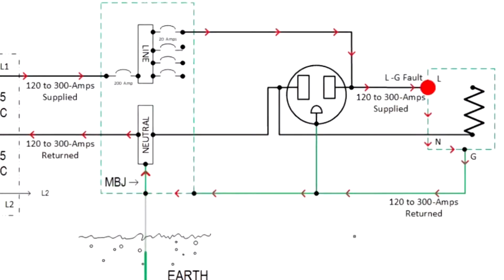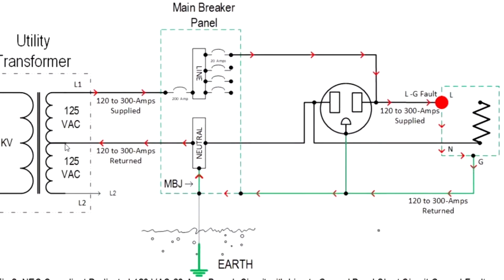Okay, now let's take a look at a fault condition. For whatever reason, the line conductor inside the chassis has fallen off and is touching the chassis, or the line cord got pinched, whatever may have happened. So now we have 120 volts in contact with the chassis, and now the ground completes the circuit. If we follow the current, we can see the current path is off the equipment ground. It goes straight back to our neutral bus inside our main breaker panel and returns to the utility. Now, since there is no more load device from line to neutral, it's line to ground, it's a short circuit. And being a short circuit, it's going to draw, should be, 120 to 300 amps.